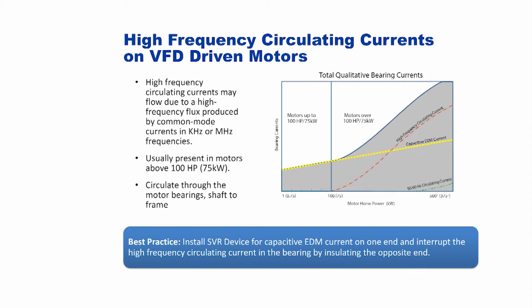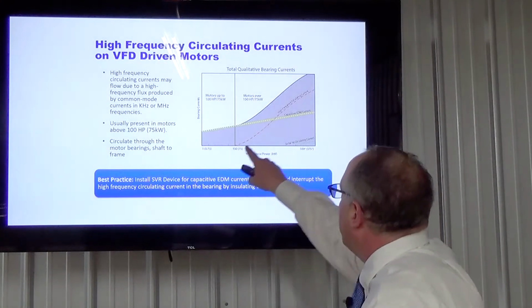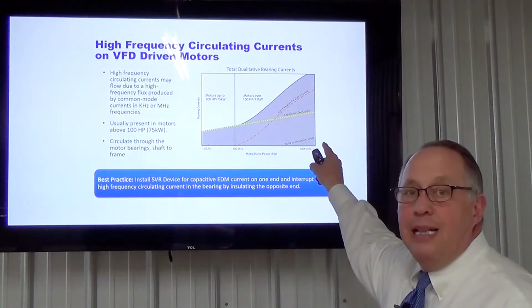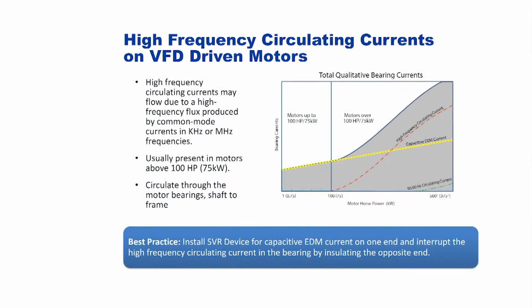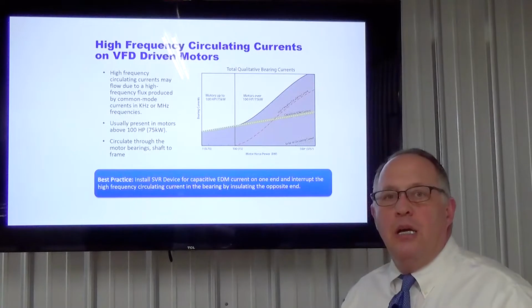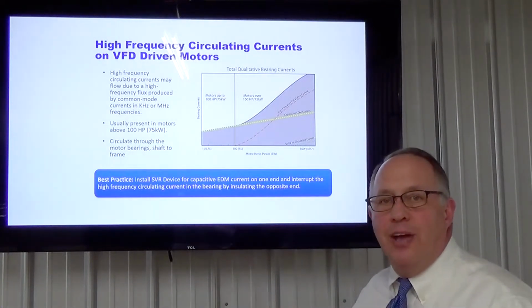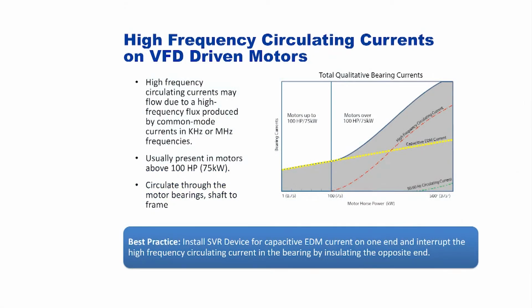High-frequency circulating currents. Not only do we have the EDM, but in larger motors, 100 horsepower and up, high-frequency currents may flow due to the flux produced by the common mode, in kilohertz or megahertz frequencies, and they circulate through the motor bearings to the shaft, to the frame. And you can see this curve along there. Capacitive current increases almost linearly with the motor size itself. The high-frequency current increases in an exponential type form, and those two are additive effects. So both of them together produce really difficult bearing currents that can cause you problems.